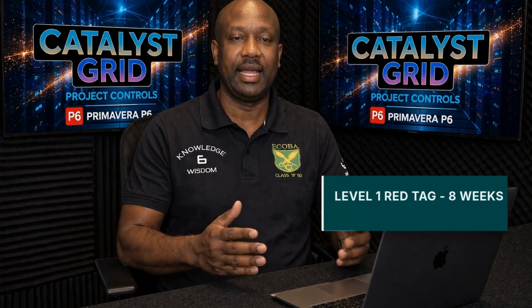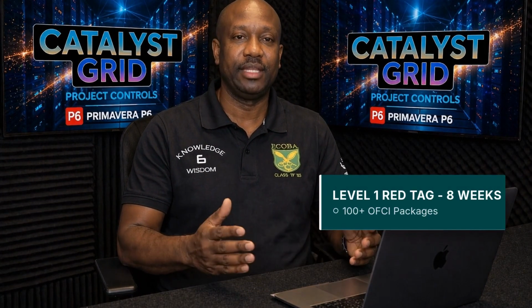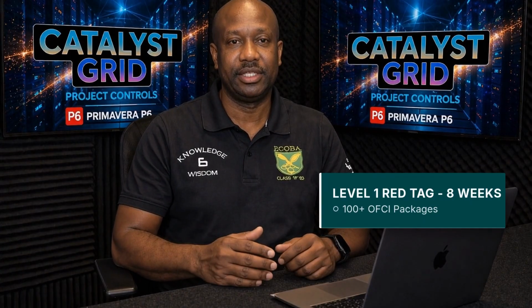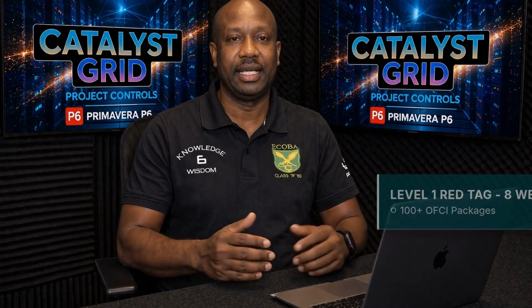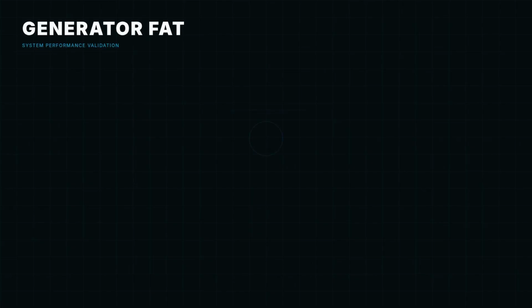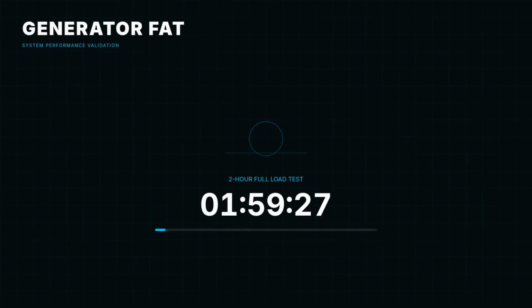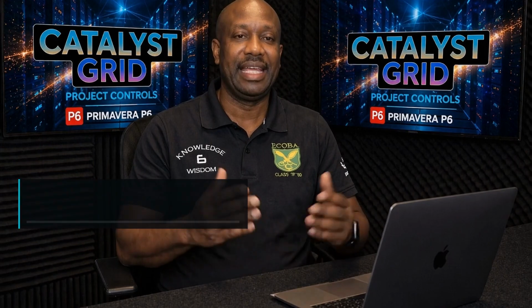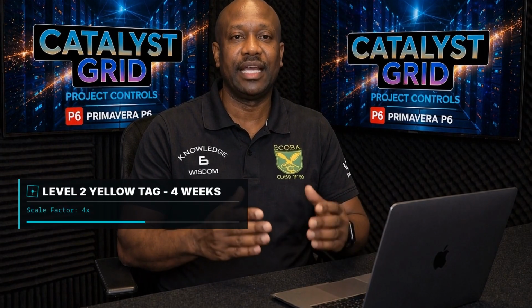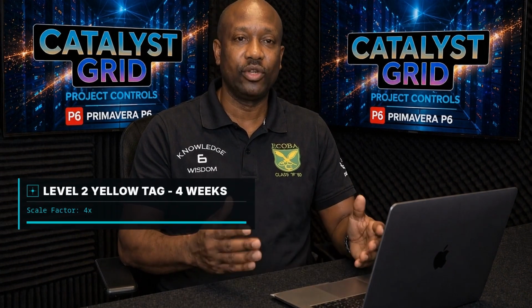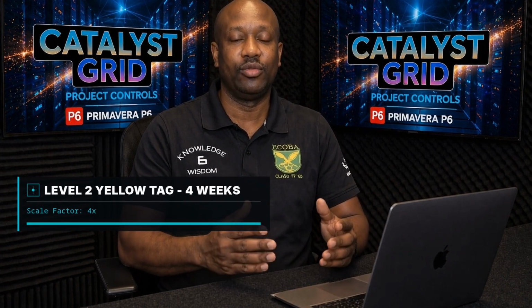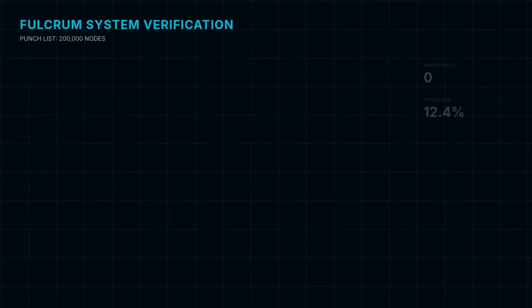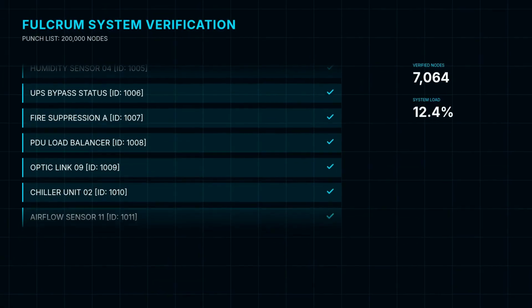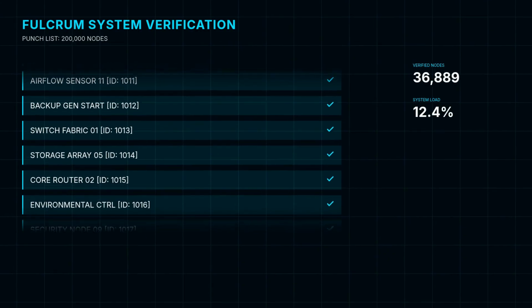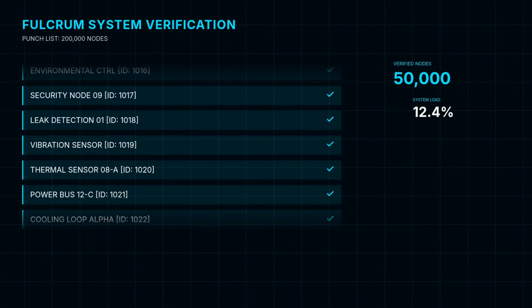Level 1, red tag at FULCRUM takes 8 weeks. We are managing over 100 OFCI packages compared to just 43 at Iron Gate. This includes 20 generator FATs. Each one requires a 2-hour full load test, with the LTA required to witness every primary equipment test. Level 2, yellow tag is where the scale of FULCRUM truly hits. We have 4 times the punch list items of Iron Gate, requiring massive coordination. DCIM sensor verification is a massive addition. All 50,000 monitoring points must be verified against the as-installed BIM model.